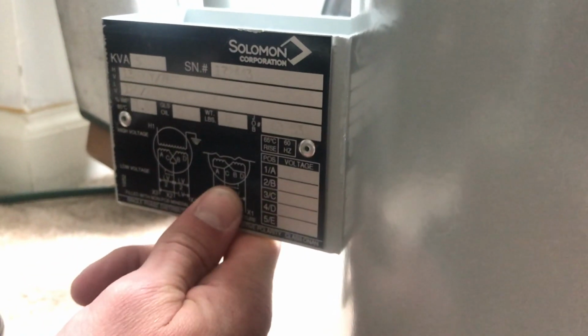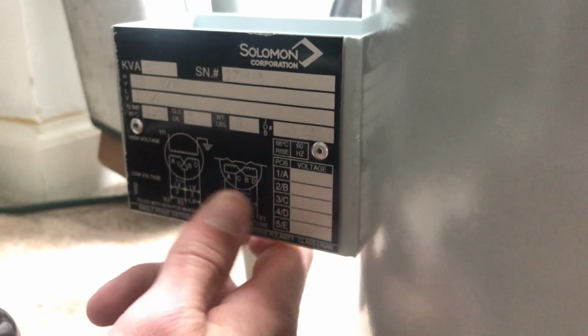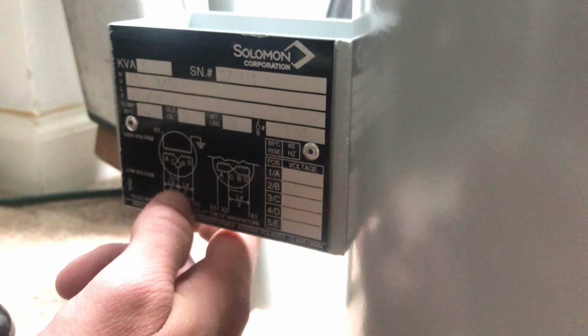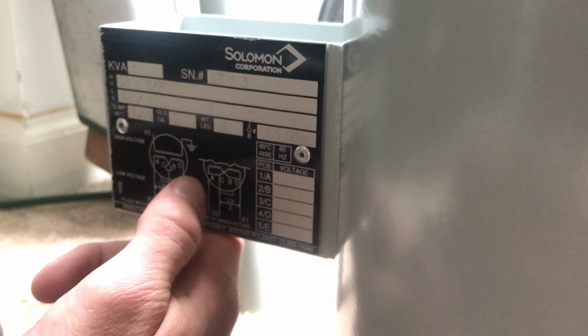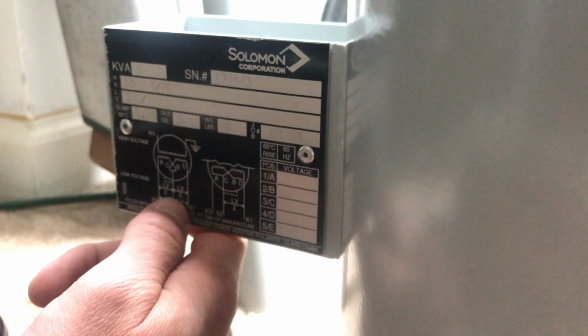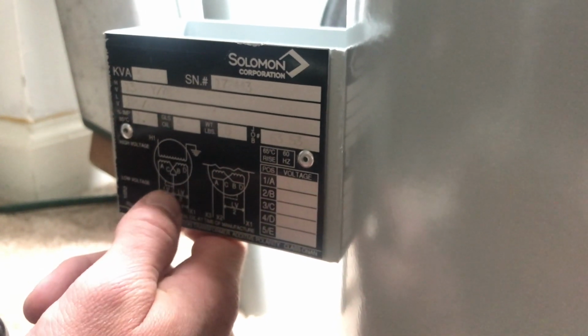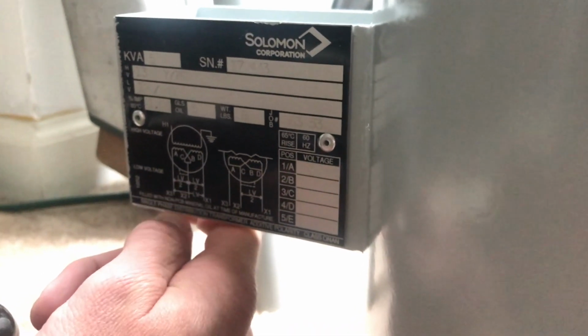Using residential transformers, they could be banked together for a 3-phase service. You could also bank a whole bunch of single-phase transformers to get a 120/240 delta with the 208 hot leg.